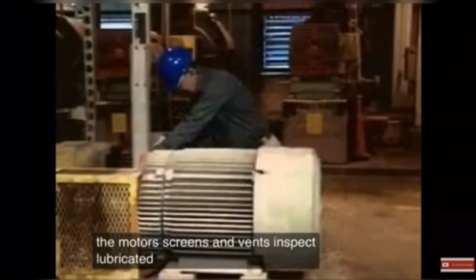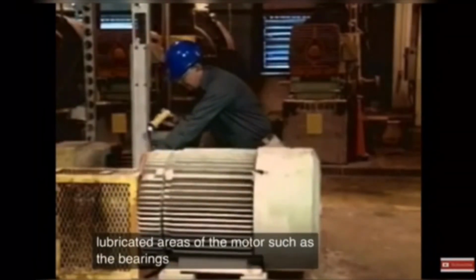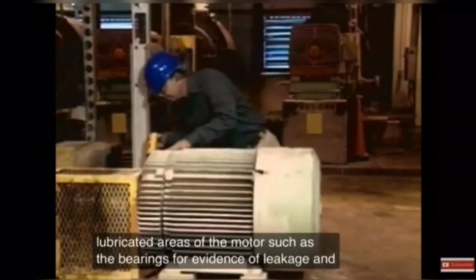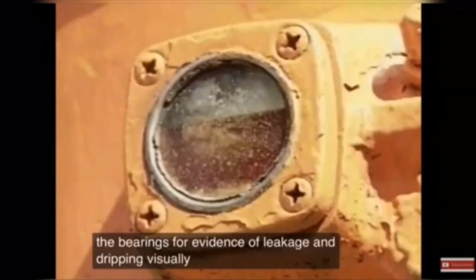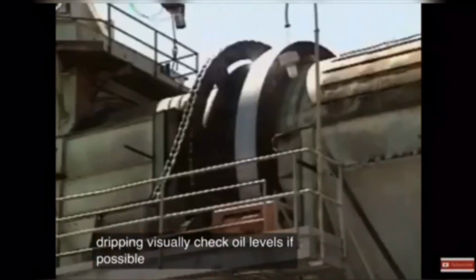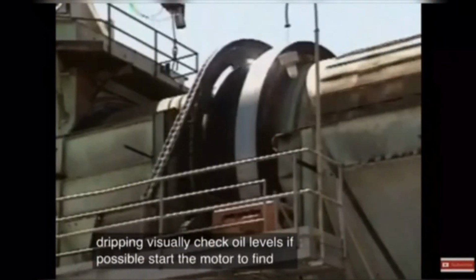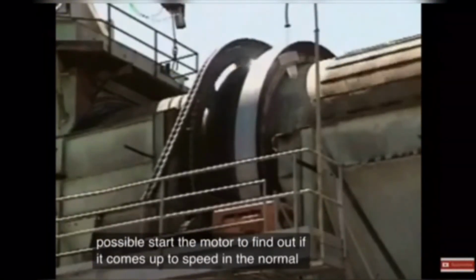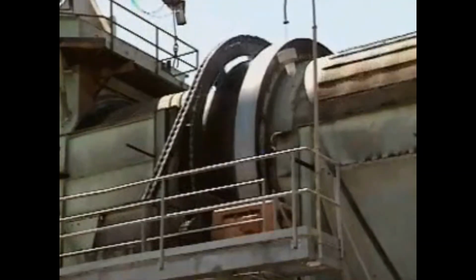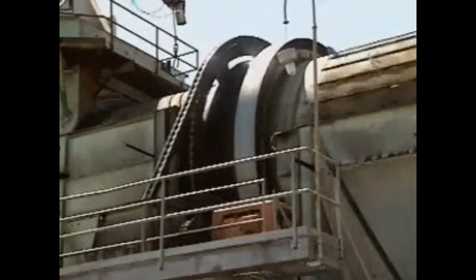Inspect lubricated areas of the motor, such as the bearings, for evidence of leakage and dripping. Visually check oil levels. If possible, start the motor to find out if it comes up to speed in the normal amount of time. Select Next to continue.